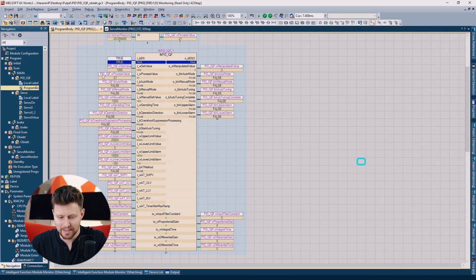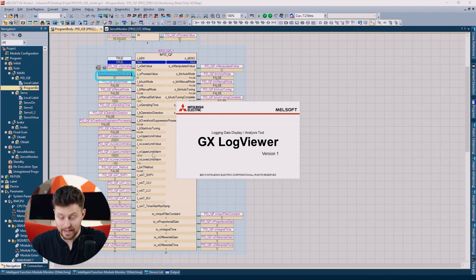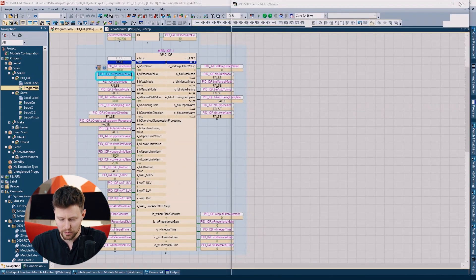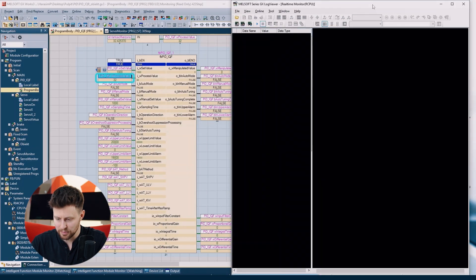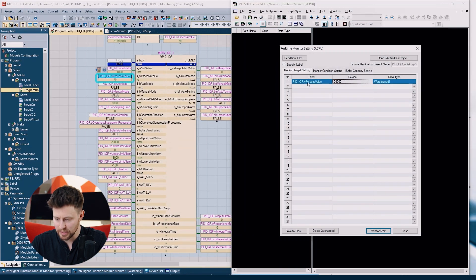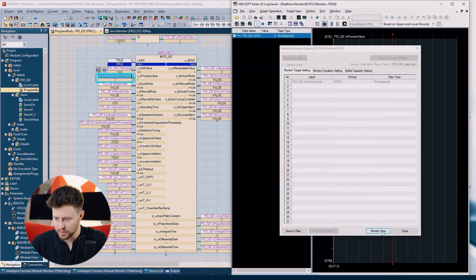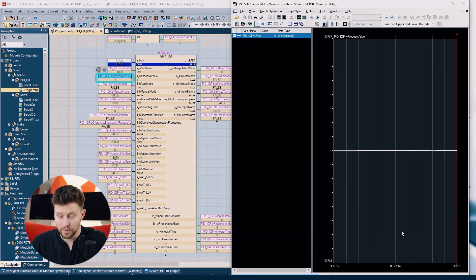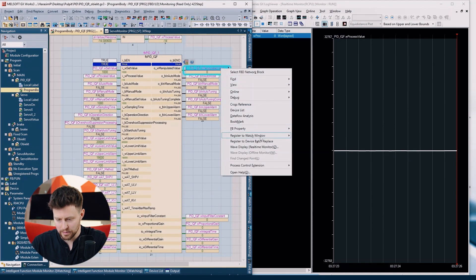How to start the real-time monitor. The easiest way is to right-click on a variable and choose the wave display option. Then the GXWorks project will be loaded into GXLogViewer. After some time we will see our variable and we can click monitor start. We started monitoring of this variable, so let's add another variable — right-click and choose wave display.